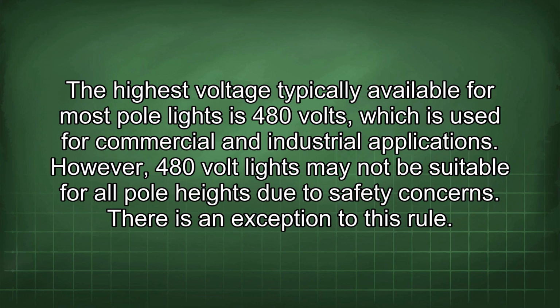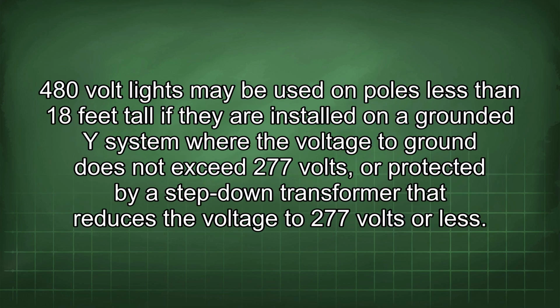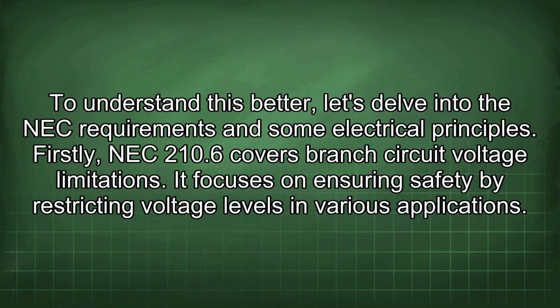There is an exception to this rule. 480-volt lights may be used on poles less than 18 feet tall if they are installed on a grounded Y system where the voltage to ground does not exceed 277 volts, or protected by a step-down transformer that reduces the voltage to 277 volts or less. To understand this better, let's delve into the NEC requirements and some electrical principles.